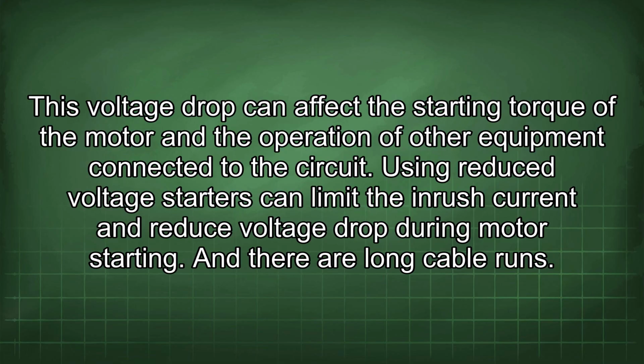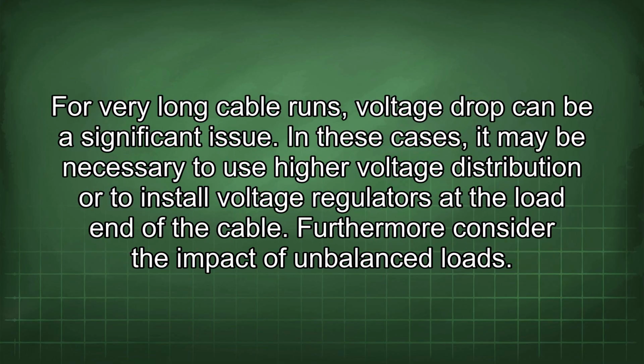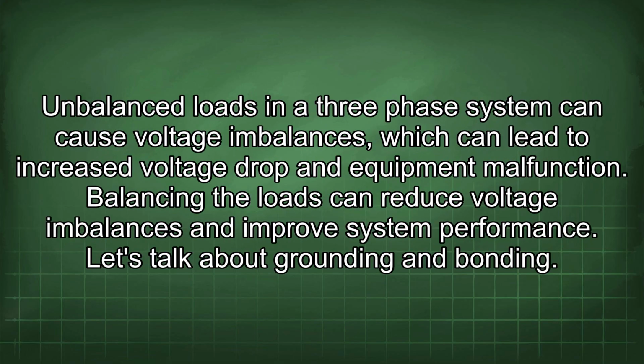And there are long cable runs. For very long cable runs, voltage drop can be a significant issue. In these cases, it may be necessary to use higher voltage distribution or to install voltage regulators at the load end of the cable. Furthermore, consider the impact of unbalanced loads. Unbalanced loads in a three-phase system can cause voltage imbalances, which can lead to increased voltage drop and equipment malfunction. Balancing the loads can reduce voltage imbalances and improve system performance.